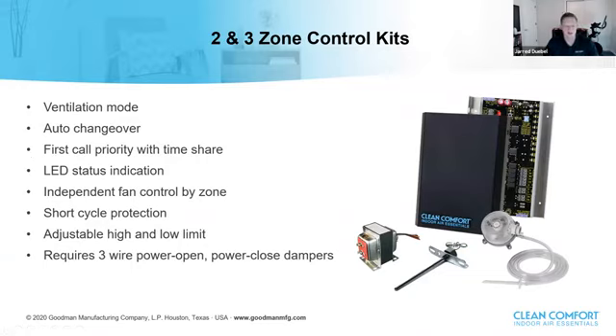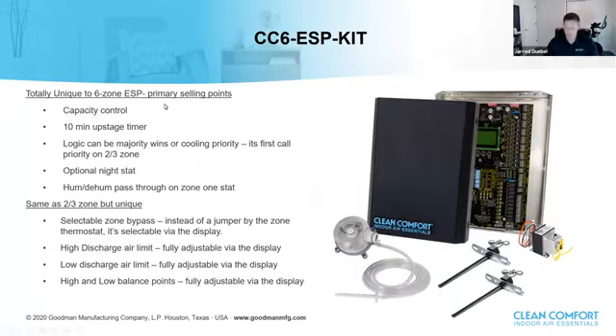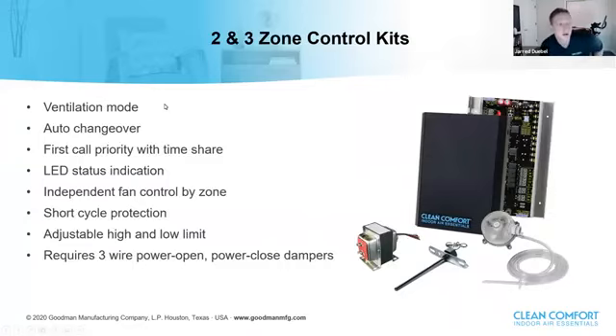Okay, so now let's talk about some of the specifics on the kits. One thing that's unique about our zone control panels is we actually offer ventilation mode, or we offer the priority to have independent fan control by zone. So what does that mean? Well, just like we zone heating and cooling calls and we open dampers where we want to push the air, we do the same thing with ventilation.